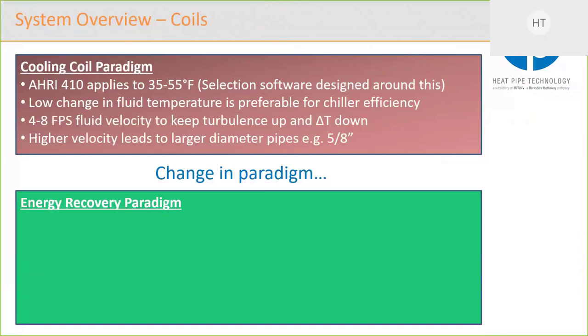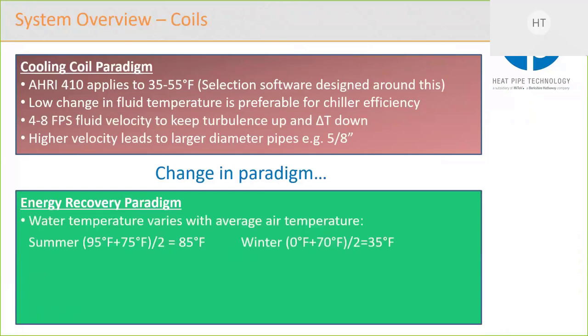So here's our change in paradigm. The first thing is that our water temperature varies substantially. So in the summer, when it's 95 degrees outside and maybe your return air is 75, well, your average water temperature is going to be about 85 degrees. In the winter, when maybe it's 0 degrees outside and your return air is 70 degrees, well, you're looking at 35 degrees. So now we're looking at a broader range between 35 and 85 degrees Fahrenheit.